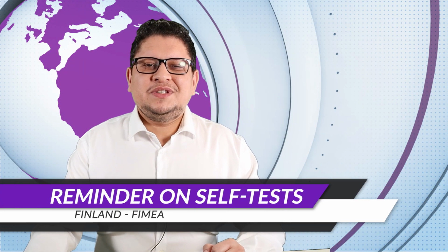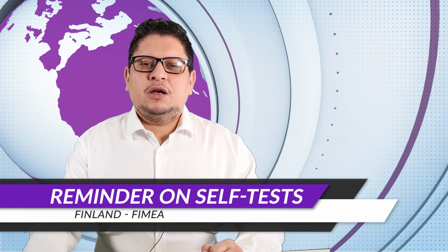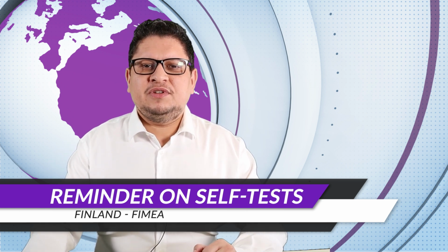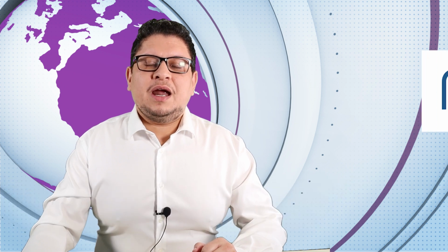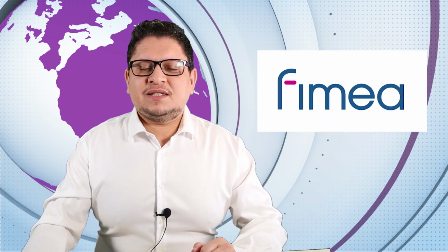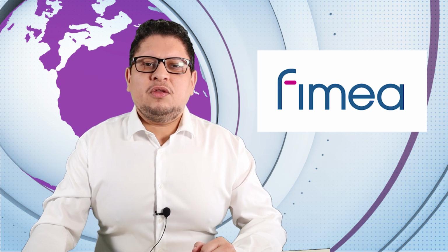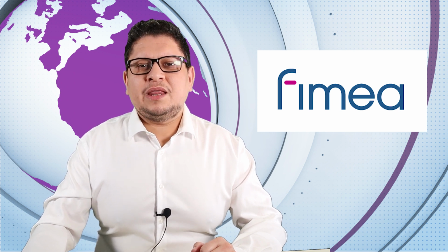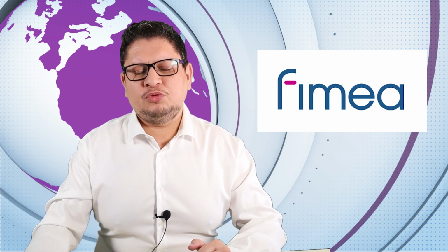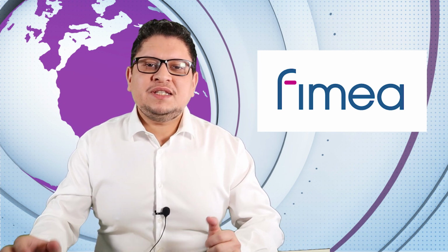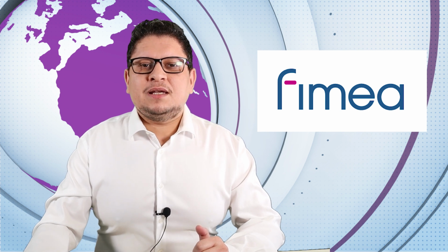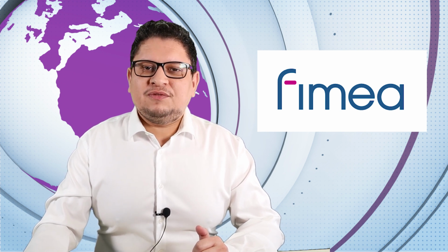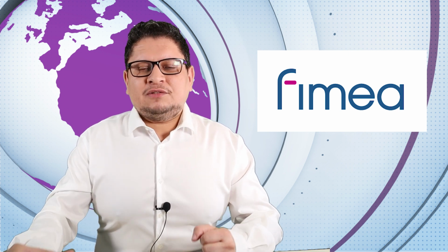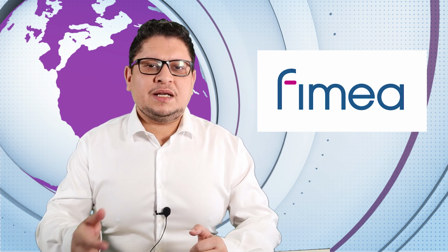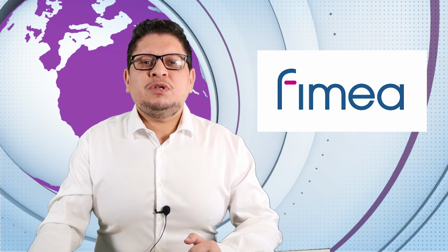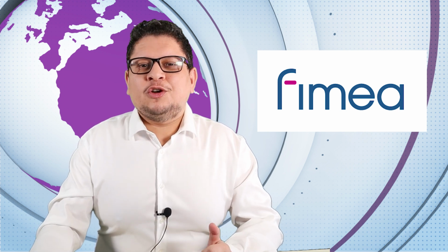And we stay on IVD for a specific reminder made by the Finnish authority, FIMEA. They are talking specifically about the self-testing of COVID-19. On this self-testing, there is a rule that they are trying to remind importers and distributors of. One of the rules is that under IVDD, those self-testing devices should be certified by a notified body. I am myself using those devices because I have some kids who go to school, and when I look at the boxes, I sometimes see a lot of issues.